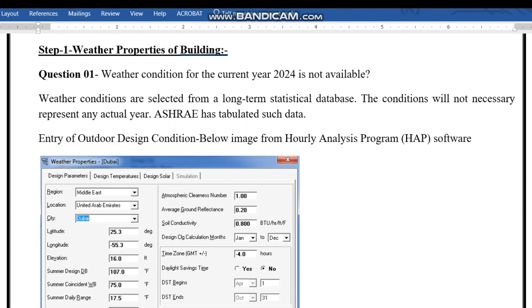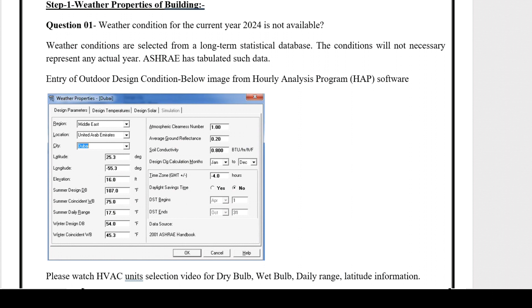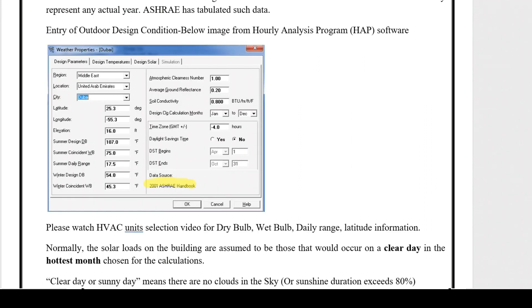Before performing any project we need to decide the weather properties of the building. Question one, which normally occurs to junior and mid-level persons: what if the weather condition for the current year 2024 is not available in HAP software? Weather conditions are selected from a long-term statistical database — it's not about 2024 or 2025 specifically; the condition will not necessarily represent any actual year. In the HAP software screenshot, I have taken the Middle East UAE and Dubai. You can see dry bulb, wet bulb, and different parameters. The data source says 2001 ASHRAE handbook.